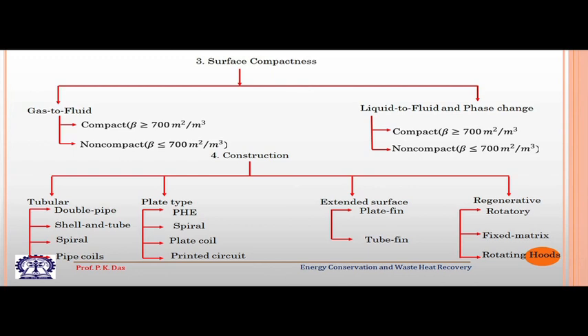Compactness is defined by a number beta. When beta is greater than 700 m²/m³ the heat exchanger is called a compact heat exchanger; when beta is less than this, it is not compact. This is an accepted definition. Compactness is very important for waste heat recovery because in many waste heat applications the delta T — the temperature difference driving force — is low, and we need a compact heat exchanger to extract a good amount of thermal energy within a given volume.